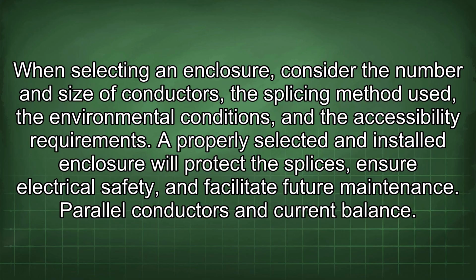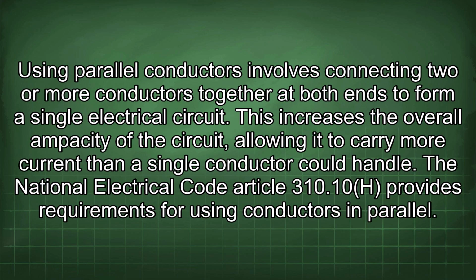Parallel conductors and current balance. Using parallel conductors involves connecting two or more conductors together at both ends to form a single electrical circuit. This increases the overall ampacity of the circuit, allowing it to carry more current than a single conductor could handle. The National Electrical Code Article 310.10(H) provides requirements for using conductors in parallel.